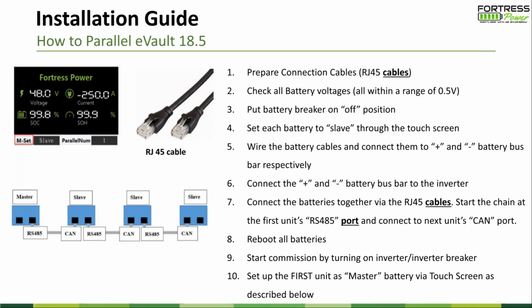So the steps we want to go with: you prepare your standard ethernet cable, and then we also want you to check the voltage, and then put all breakers in the off position, and then set all your batteries as slave. You see the LED is a touch screen. So you touch M set, it will let you set as a master or slave. We want to set all to slave. And then we start wiring the battery cables positive and negative, as I mentioned in the last few steps. Then we connect the communication cable in between. And we want the customer to reboot the whole system. So just turn the BMS off and turn the BMS on. Push the button in front of the batteries.